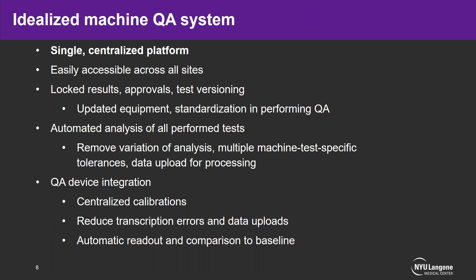With that in mind, we started thinking about what an idealized machine QA system would look like. Ideally, you'd have a single centralized platform, easily accessible across all sites, with locked results, locked approvals, and test versioning. It would be simple to update equipment and standardize QA. You'd have automated analysis removing variation, enable machine-specific test tolerances, and automate data uploading. We also hoped to incorporate QA device integration — centralizing calibrations, reducing transcription errors, and enabling automatic readout of devices compared directly against a baseline.